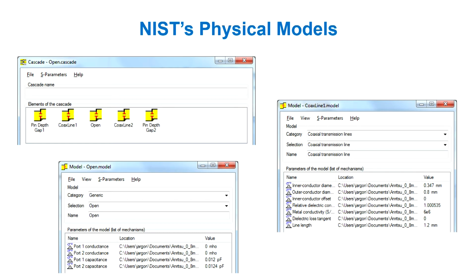This is basically showing an offset open. So for our offset open, it's like a 2-port open here. We've got an open standard, and then we actually have to cascade coax lines because of the offset lengths of this open. And then we also have models for the pin depth gaps on both sides. So our overall offset open is a cascade of 5 different models. The open itself is just a simple open where you can put in conductance and capacitance. And then for the coax line, which represents the offset, you put in a number of inputs such as your inner conductor diameters, outer conductor diameters, and lengths, and so forth. So here we can create our physical models, and they're all based on closed form expressions that have been input into the uncertainty framework.